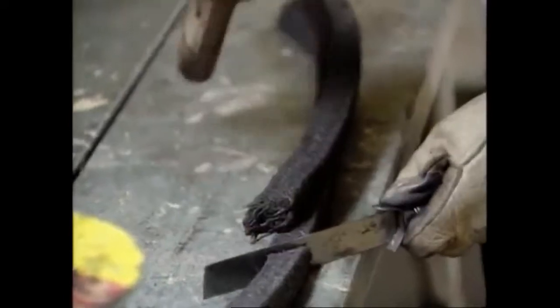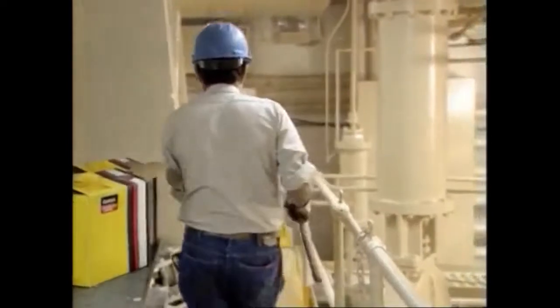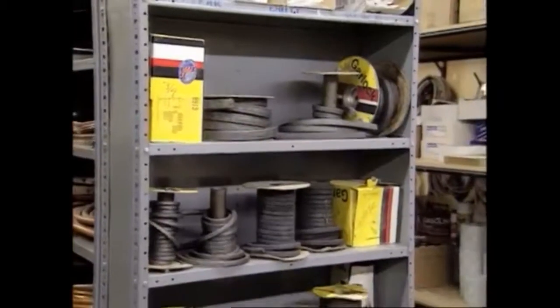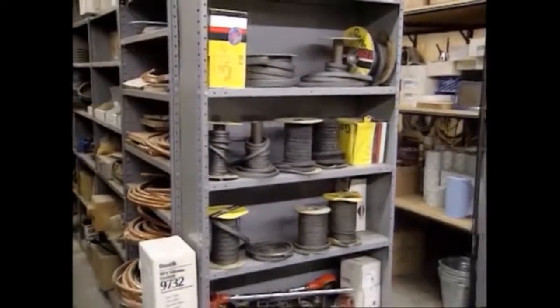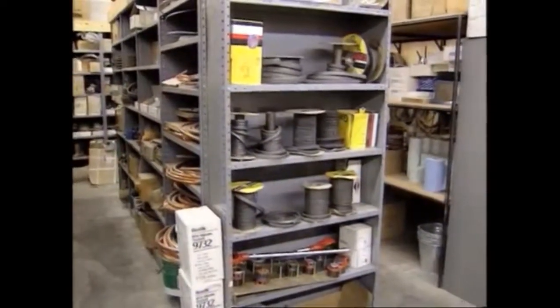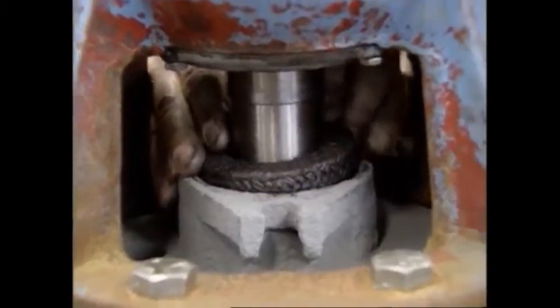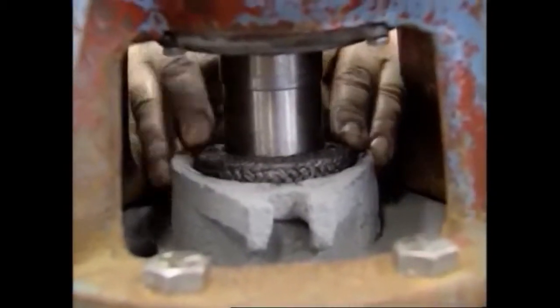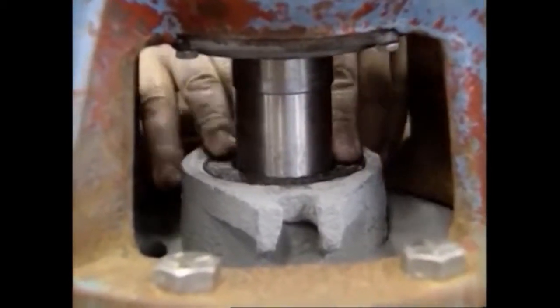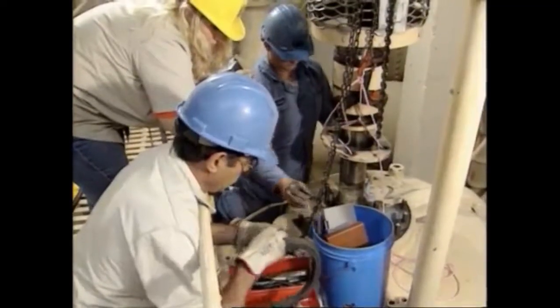There are probably over 500 different types, grades, manufacturers, and styles of packing on the market today. Packing can be round, square, loose, pointed, or almost any size, shape, or form. It is manufactured from jute, hemp, Teflon, asbestos, rubber, lead, or almost any other materials. The pump manufacturer should recommend the proper packing based on the type of pump. Selection of a packing material is also based on what is being pumped, for example, water, wastewater, acid, alkali, scum, sludge, or grit, or other material.